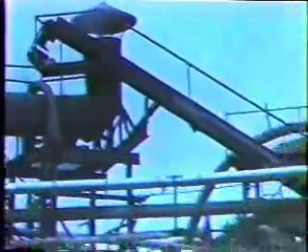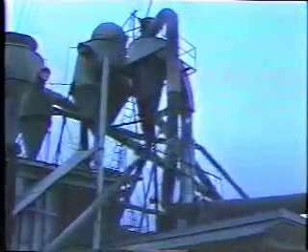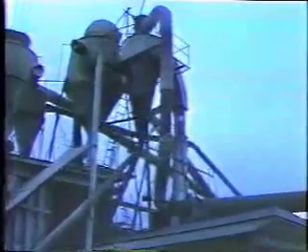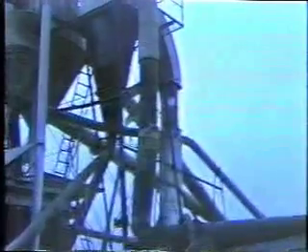The hot flue gases are then extracted and flow through this almost horizontal smokestack. At the same time, green sawdust is input by screw auger into the other end of the smokestack. Inside the stack, pieces of angle iron are attached to the pipe. Although it's hard to see, the stack is actually mounted on a ring mechanism which constantly rotates the stack. Since the stack is at a slight decreasing angle from the point the sawdust is input back to the plant, the green sawdust is carried by gravity towards the plant. The rotation of the stack with the mixing action caused by the internally mounted angle irons then allows the hot flue gases to dry the green sawdust as it moves towards the plant. Upon arrival at the plant, the dried sawdust is then immediately input into the boiler system of the plant and used as fuel.